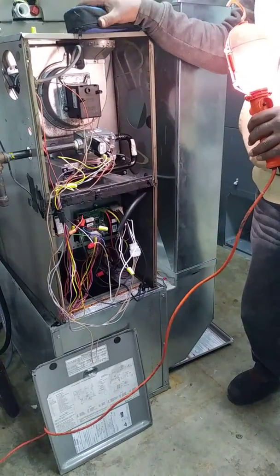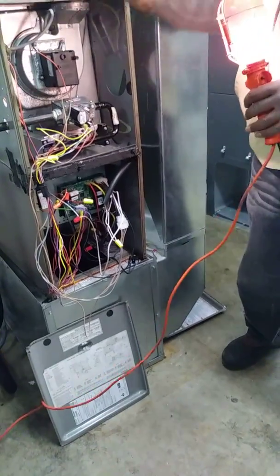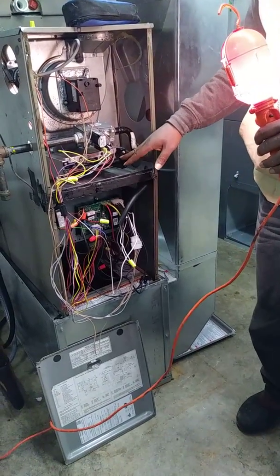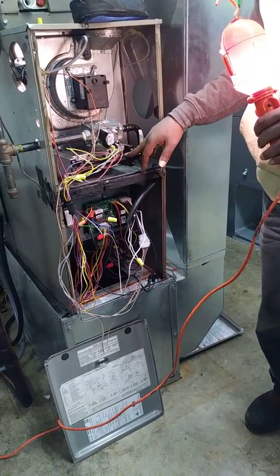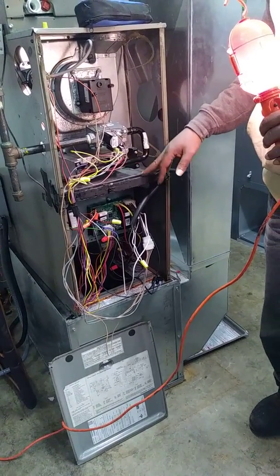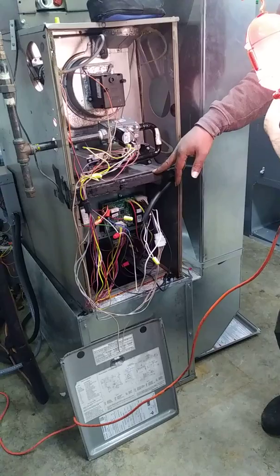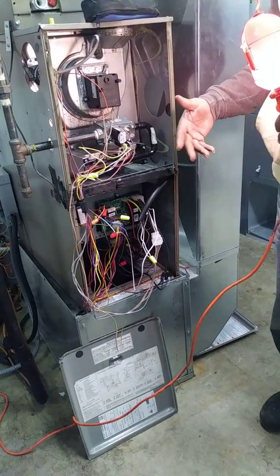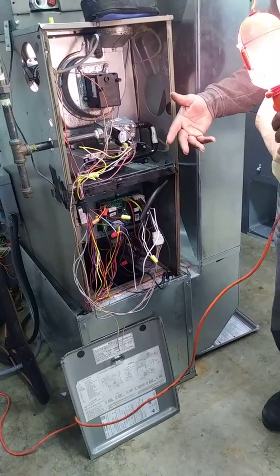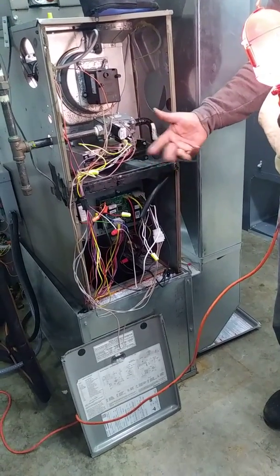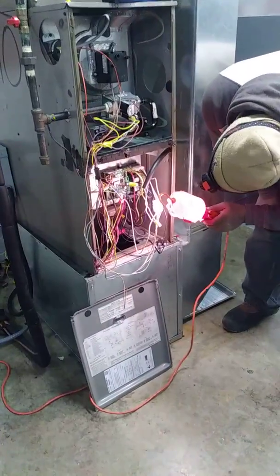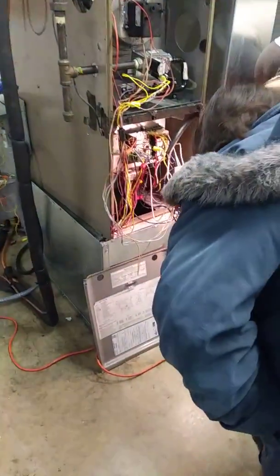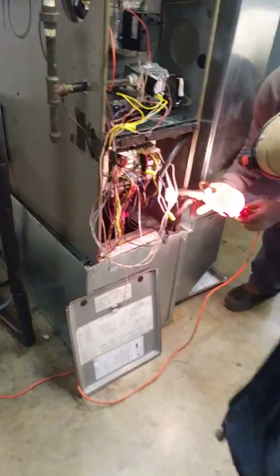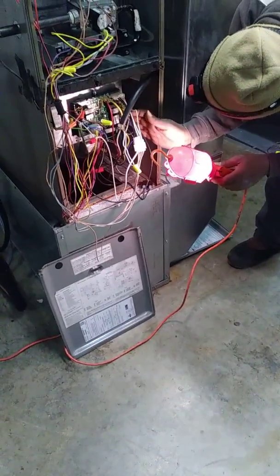If you don't hear the relay click for the blower motor after you get ignition, and if the flame sensor is not the problem, like I said, if the blower motor doesn't come on, you check the capacitor, check the blower motor, but you also have to listen for a click for that relay, which is sending the signal for the blower to come on. And find the one that's for heat for the blower motor. It looks like this one is blue. Blue is used for heat. So you go across the blue, and you will go across the white from the blower motor, and make sure that it's getting power to them.